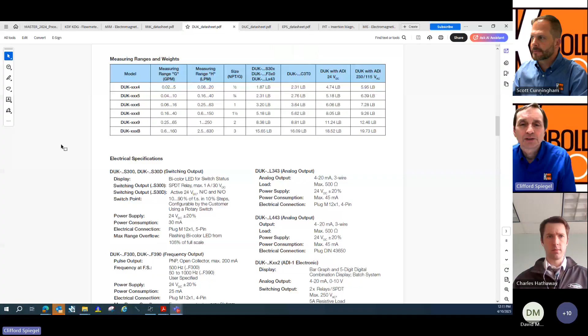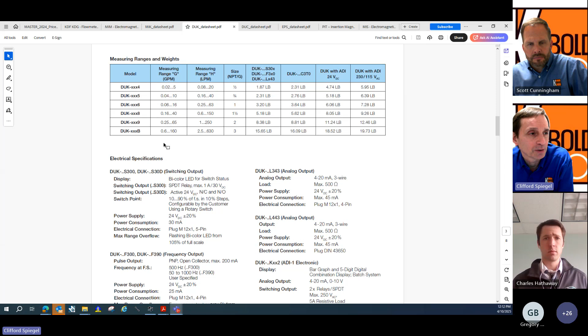Yep, okay, so for example if we pick the second one down here, on the high end it's 10 GPM. So it's real simple - you take 10 and divide it by 0.04 and you get 250. So on this particular meter, it can measure from 0.04 GPM to 10 GPM, which is a factor of 250, and that'll carry down the line. Some of these may vary a little from rounding, but that's tremendous - not all flow meters can do that.